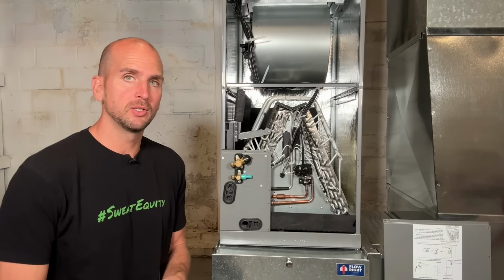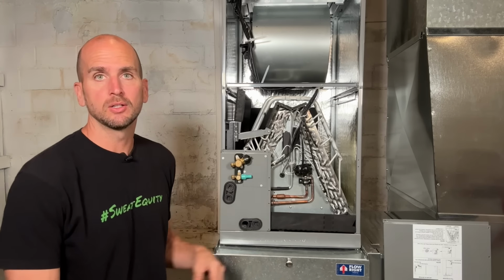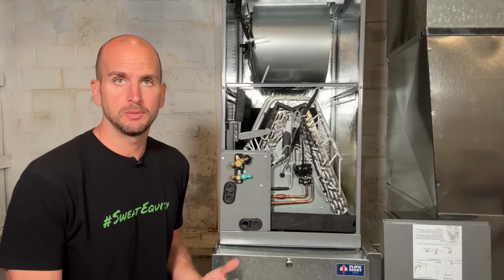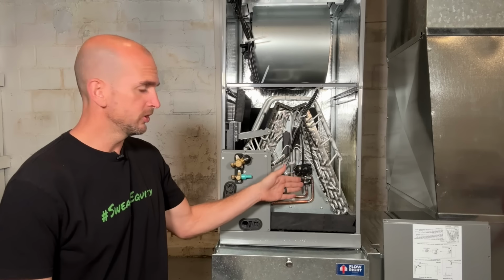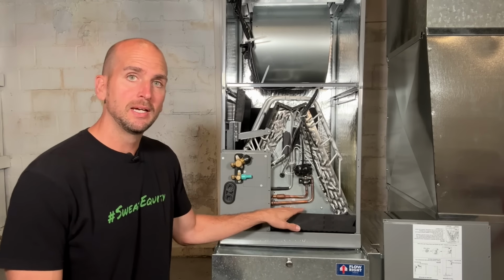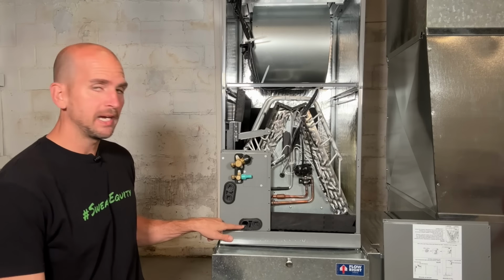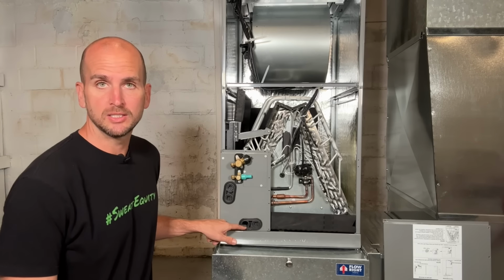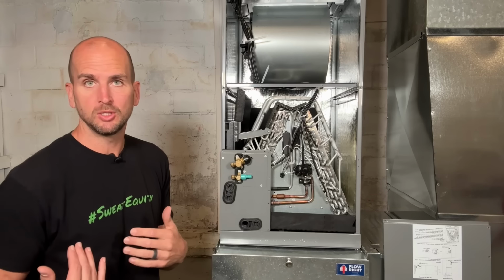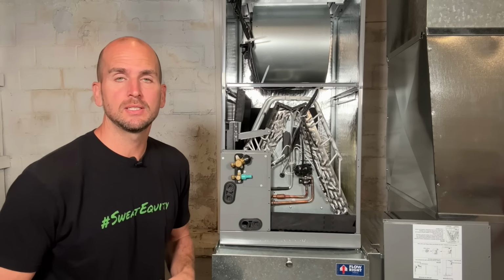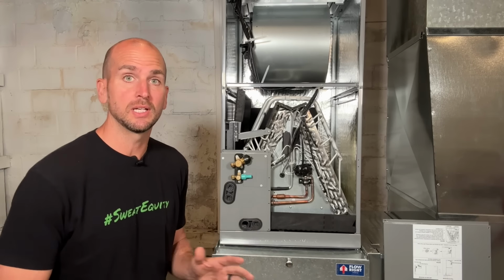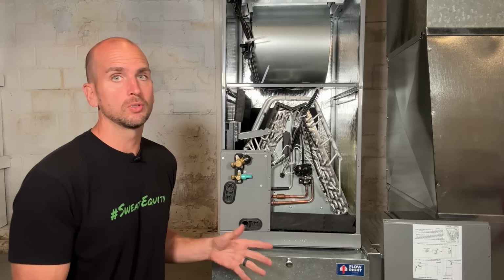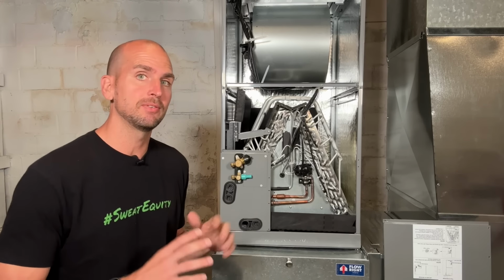Now, if you're not familiar with the coil setup here, it's very common for condensation to build up. That condensation will fall down into a plastic pan, and then from that pan, we need to have an outlet for that condensation to get away from the unit. If you do not properly drain this, that can lead to all sorts of issues and a complete mess on your floor, or if you're installing this up in the attic, even bigger issues.